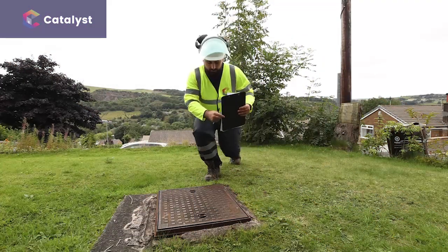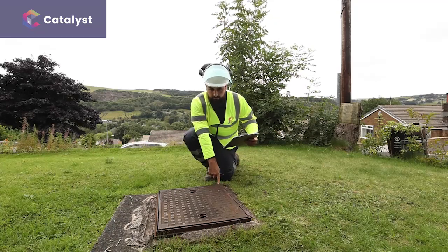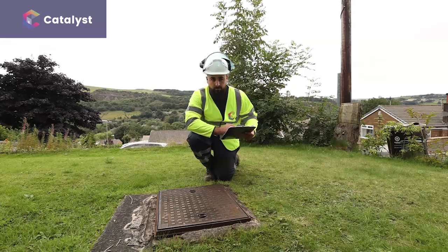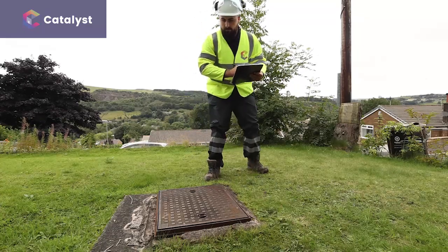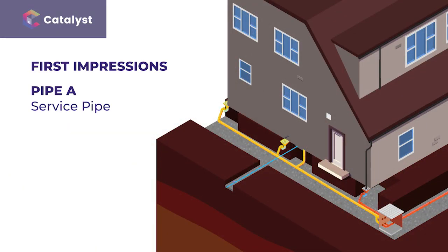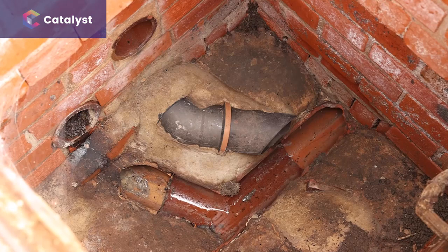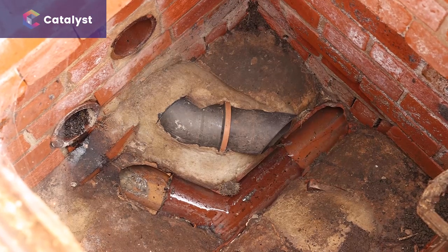Drawing on experience and an initial visual inspection, a drainage engineer can often make a good guess at the structure of the drainage system at a property like this. First impressions here are that a service pipe down the side of the house picks up the surface water and foul water and then empties into the chamber, with the front corner gully feeding into the chamber independently. The only way to be sure though is to carry out a thorough CCTV survey. Based on what we can see in the manhole, the drainage in this property is made up of clay pipes.